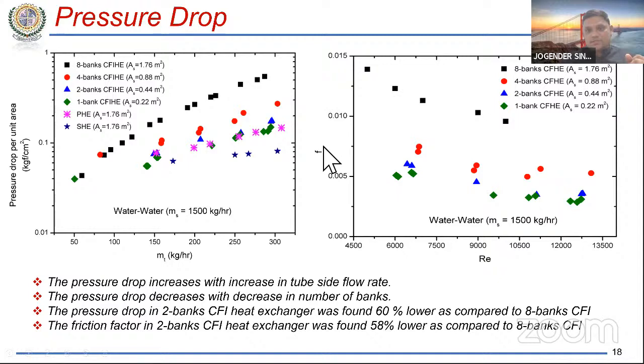Okay, and similar is the case for the friction factor with the Reynolds number here. We can see that the friction factor always decreases with the Reynolds number. This is a very well known behavior. And you can see here also that the 2-bank heat exchanger and 1-bank heat exchanger have a similar kind of friction factor. So we noted that the 2-bank CFI heat exchanger has approximately 60% lower pressure drop as compared to the 8-bank heat exchanger. At the same time, we are having approximately similar performance in terms of heat transfer coefficient. Also, the friction factor here is found to be lower than that of the 8-bank heat exchanger. You can see here it is very high, and here it is approximately 60% lower.